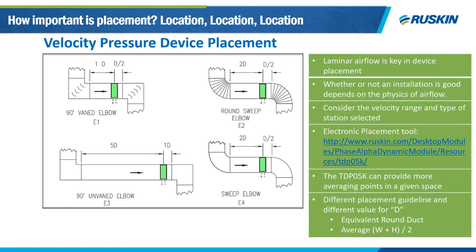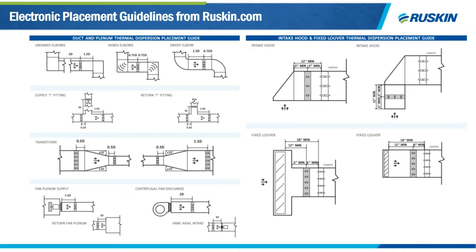Thanks Spencer. The basic math can be useful for design considerations like sizing for airflow, but another key design consideration is where you place one of these devices. Airflow devices require laminar airflow to read accurately, which is a function of physics based on obstructions in your duct and equivalent duct diameters. Here you can see examples for velocity pressure devices for various types of elbows. In cases of limited space, it may be a good idea to consider vaned elbows over unvaned to help provide laminar airflow more efficiently.